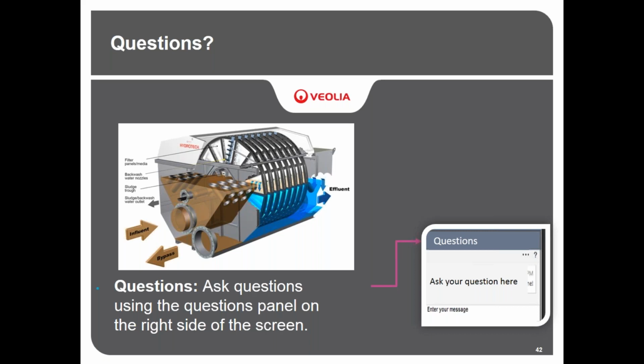Okay, we have another question. It's related to the backwash. Can you talk about the volume of water that is used in backwash? Sure. We estimate that the backwash volume is about 3% of the forward flow. We don't talk about backwash time because the filter continues to filter while it's backwashing, so it's not like there's downtime. So we usually talk about the percent of the flow that is used for backwash. It's estimated in a typical application to be about 3%.